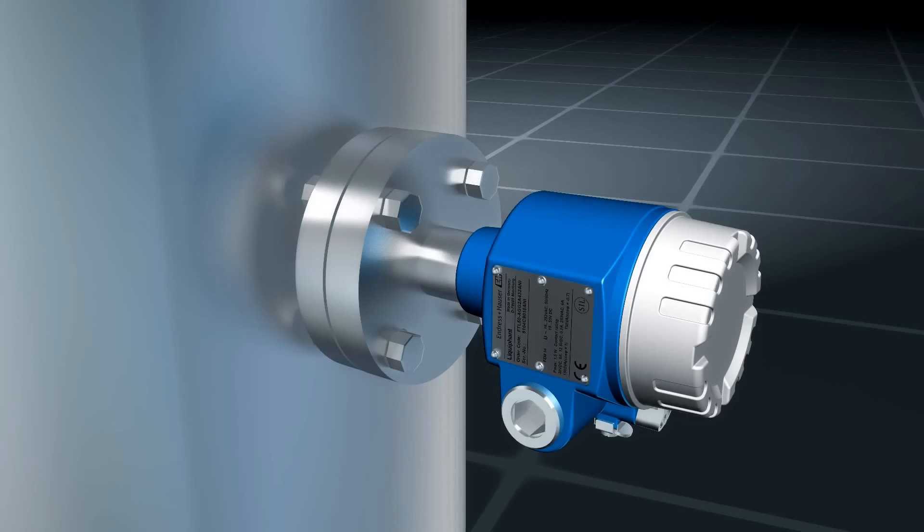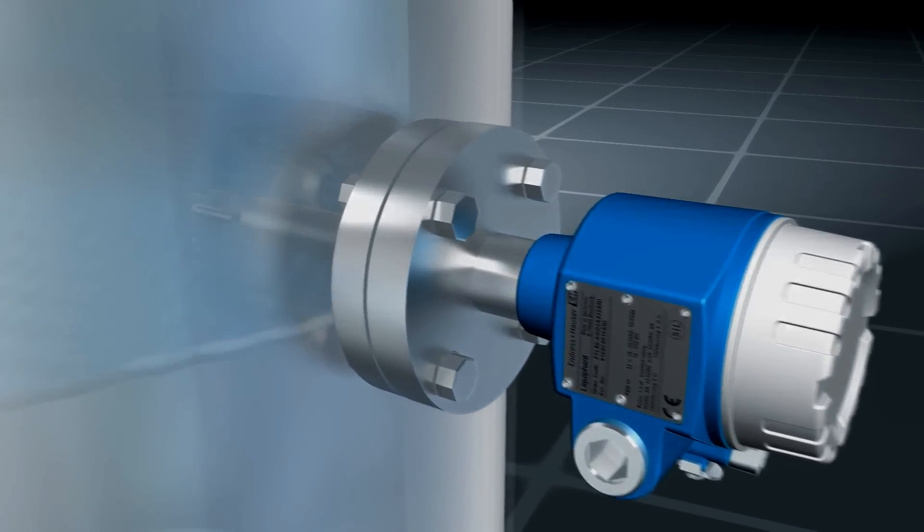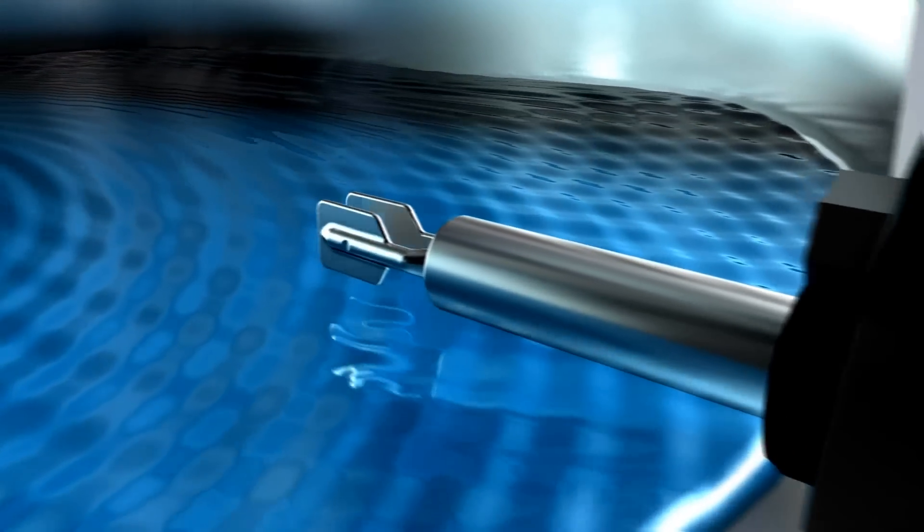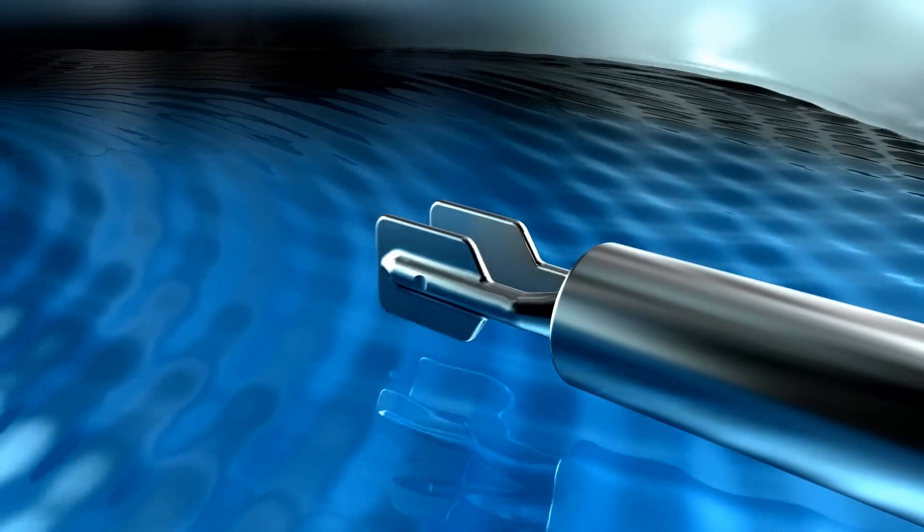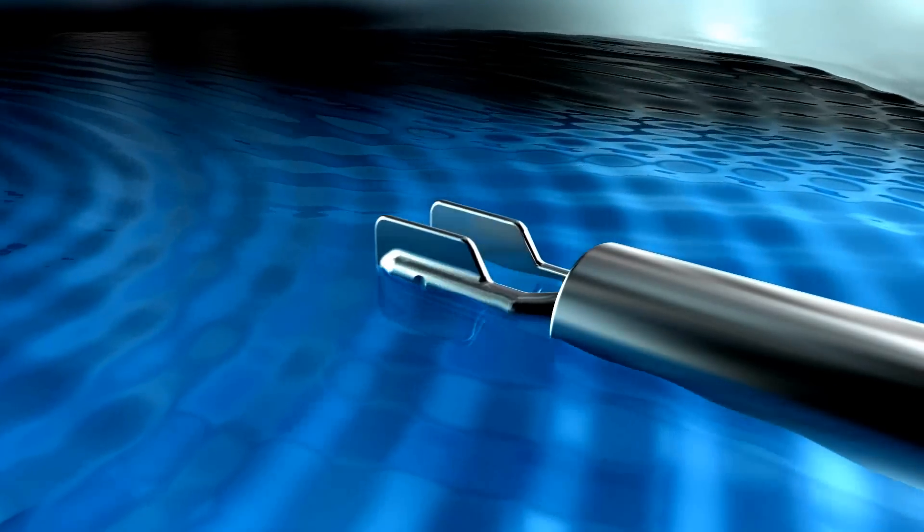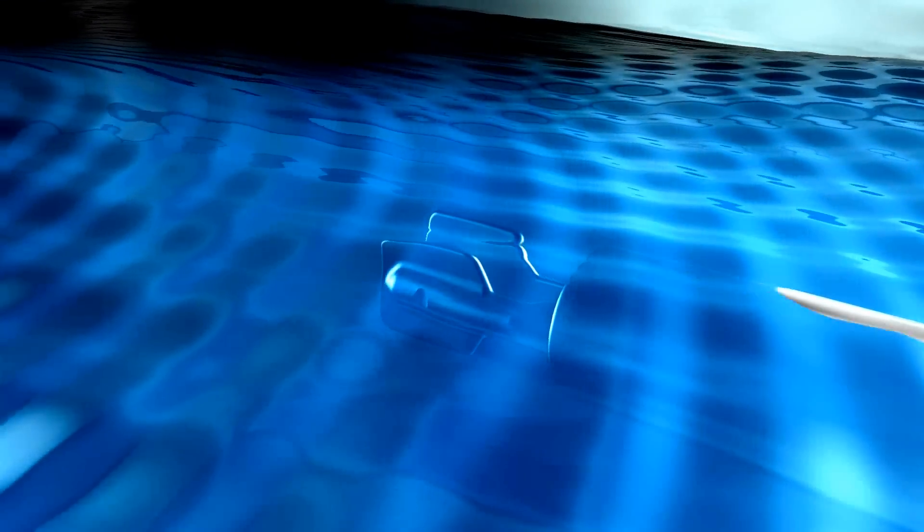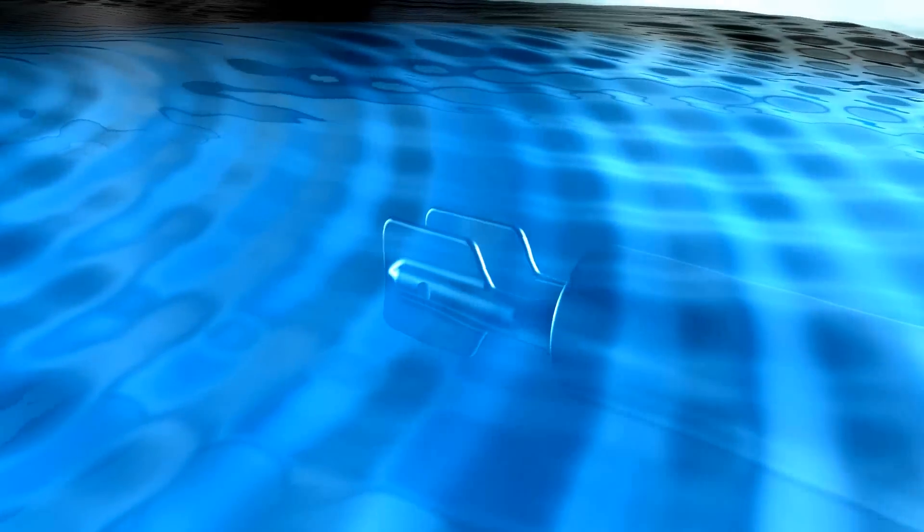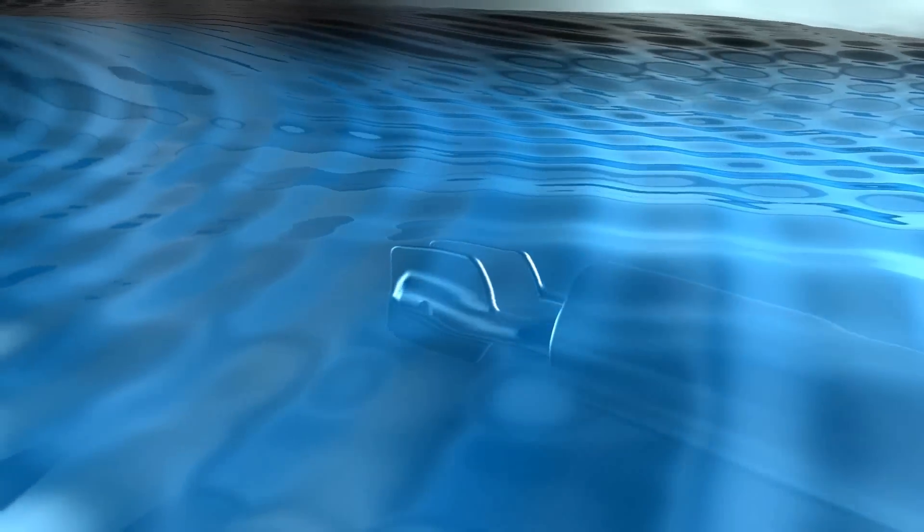Vibronic instruments monitor point levels in tanks, containers, and pipes. A sensor in the form of a tuning fork is excited to its resonance frequency. The vibronic measuring principle in liquids is based on the resonance shift of a piezo-electrically excited oscillation system.